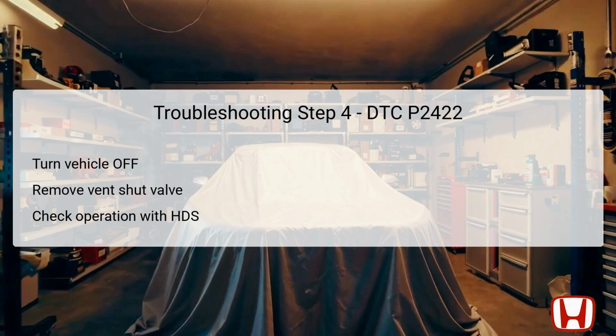Inspect the valve thoroughly to confirm it is free of corrosion and operates smoothly. If both conditions are met, this indicates that the valve itself is functioning correctly. Should there be any signs of corrosion or function failure, it is necessary to replace the vent shut valve.